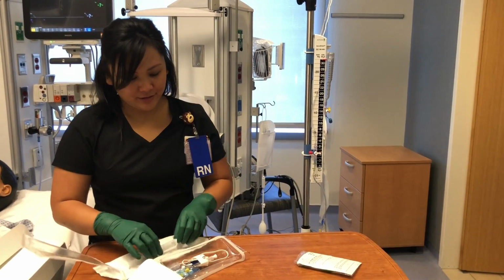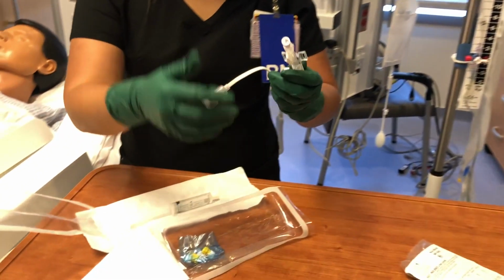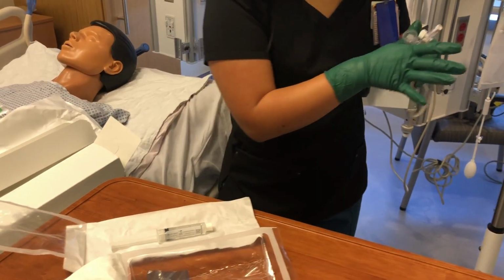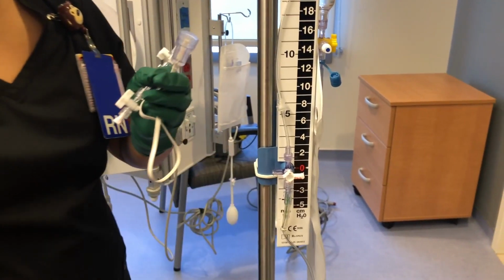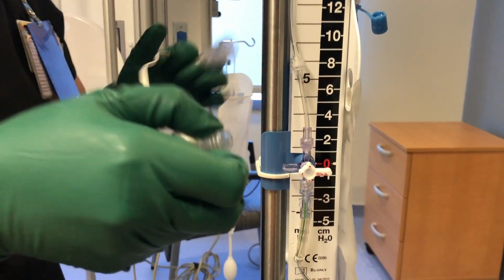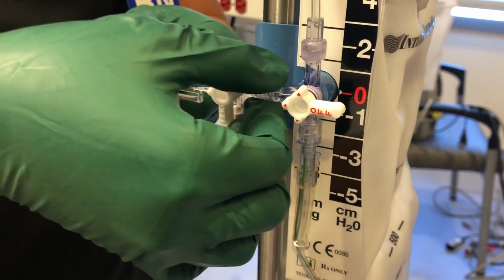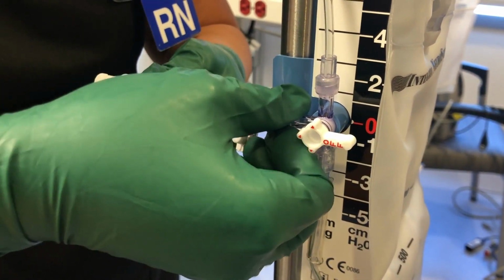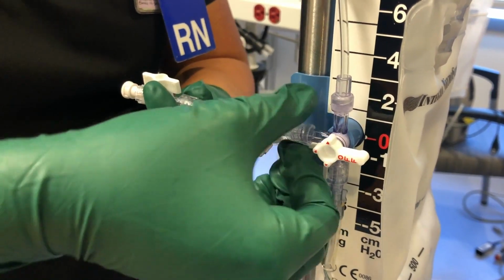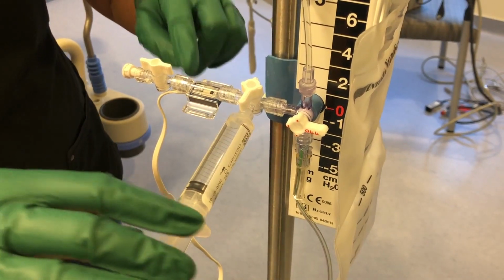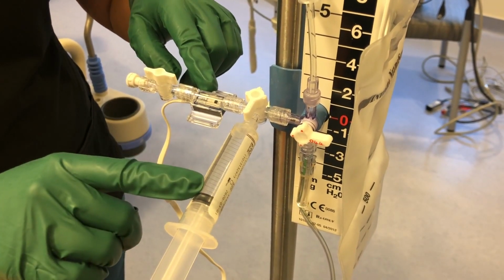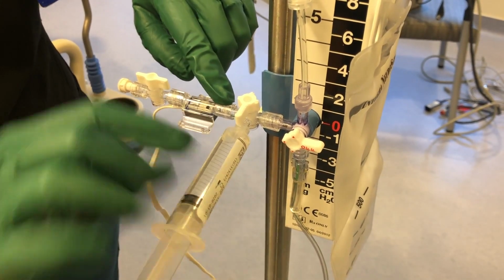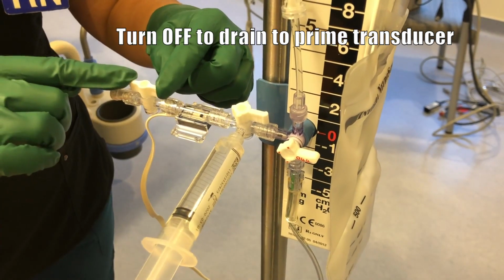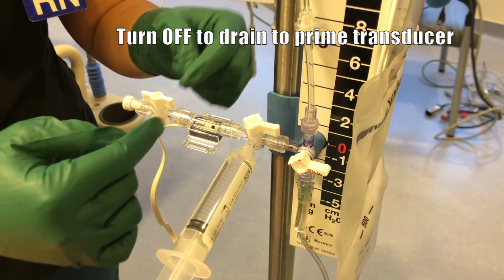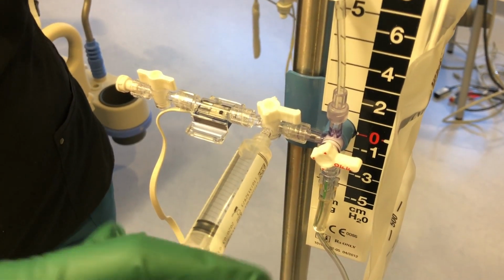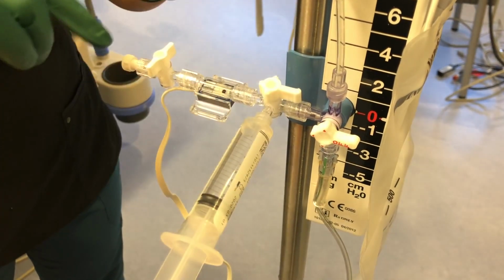You need to prime the AccuDrain. So first, prime the transducer. And by doing that, you'll need to connect it to the AccuDrain. Make sure that the connection's well. Once you connect the transducer to the drainage system, you have to connect the sterile saline syringe to the connector here. You turn it off to the drainage bag. These arrows will be pointing towards the system and towards you, so you know that this side is open, and you can go ahead and flush onto you. Then you make sure you close this port so you know that it's sterile and nothing will come out.